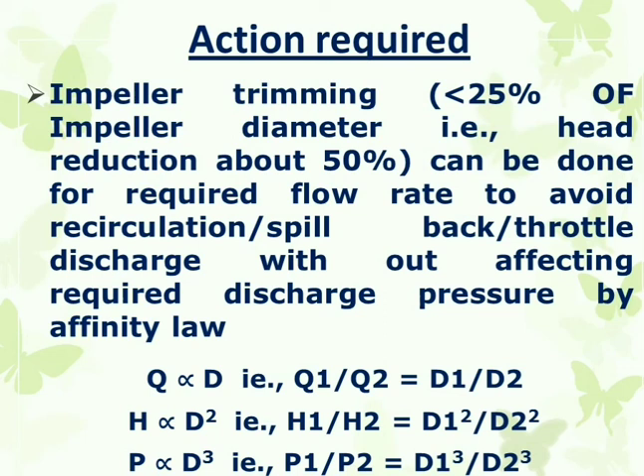The third option is to reduce the impeller diameter. By the affinity law, flow Q is directly proportional to impeller diameter, head is proportional to the square of impeller diameter, and power is directly proportional to the cubic power of impeller diameter. So we can reduce the diameter of the impeller, which will reduce the pumping rate, discharge flow, and discharge head. We should not trim the impeller greater than 25% of the original diameter. For example, for a 100 mm impeller, we can trim it up to 75 mm only and should not go to 74 or 70 mm.